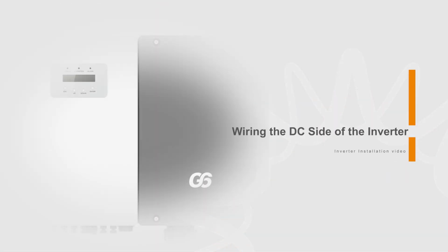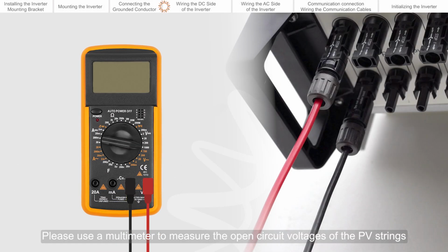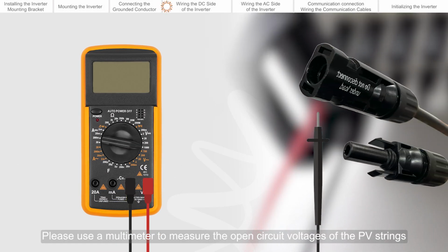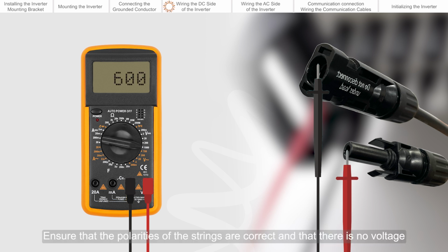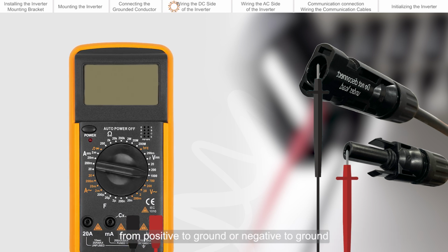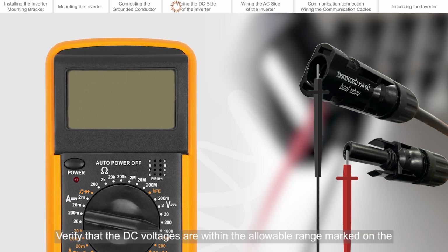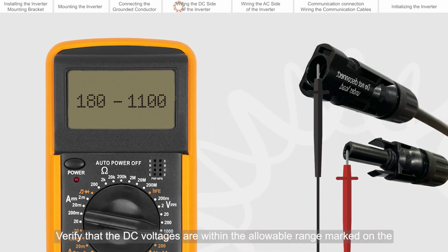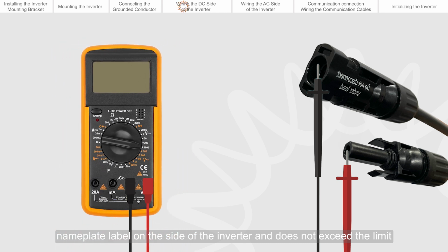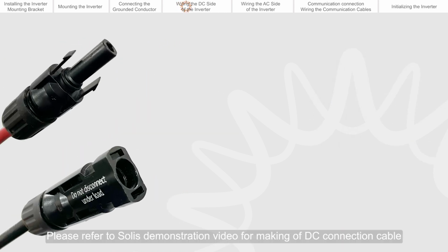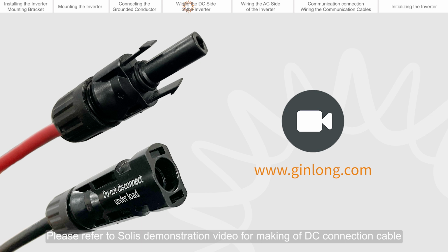Wiring the DC side of the inverter. Please use a multimeter to measure the open circuit voltages of the PV strings. Ensure that the polarities of the strings are correct and that there is no voltage from positive to ground or negative to ground. Verify that the DC voltages are within the allowable range marked on the nameplate label on the side of the inverter and do not exceed the limit. Please refer to the Solis demonstration video for making the DC connection cable.